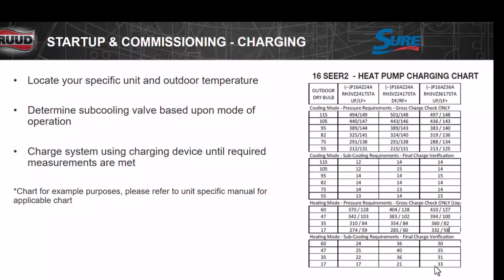On this chart, everything is really close. You see the different subcool I mean? But on some of them, you have a drastic difference, especially in the heating mode. Let's say we're charging it in the heating mode. Our target subcool here is 22. If it's right flow or downflow, it's 36. See the difference?